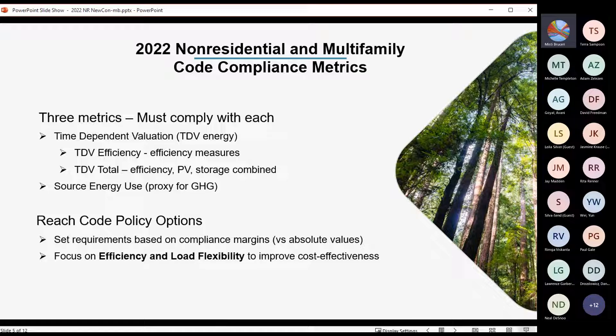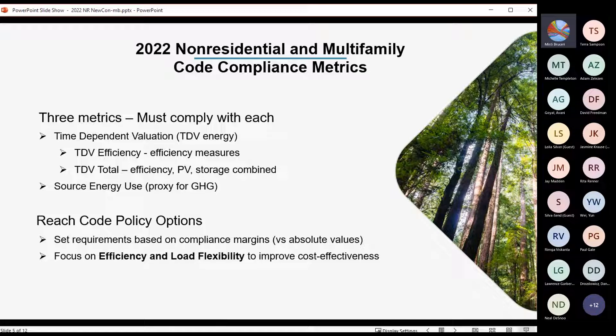The first metric is time-dependent valuation. Non-residential and multifamily had used TDV as the metric for compliance already. In 2022, for non-residential, there's now PV and storage required, so the metric has been split into two components: TDV efficiency, which includes all impacts of efficiency measures, and TDV total, which includes efficiency plus PV and storage. In addition, a source energy use metric has been added — that hourly source energy use is actually a proxy for GHG savings and emissions. You have to meet each one of these individually.